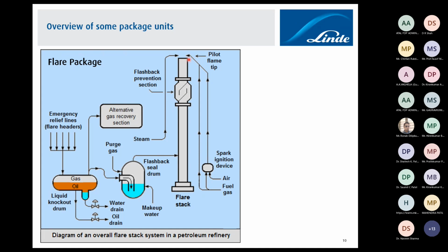Apart from these, on the top you will always find some burners, or pilot burners. Air and fuel from the grid are fed up to the top level, and you will find a spark plug, which is not shown in the picture. The spark plug ignites the fire, and it is just like your domestic gas burner. So you have to keep it on continuously. As and when any PSV pops up and gas is liberated, it should be burned out immediately. So this is the working principle. And in many typical industries, you might have seen a long, very high elevated stack with something continuously burning. That is nothing but a flare.